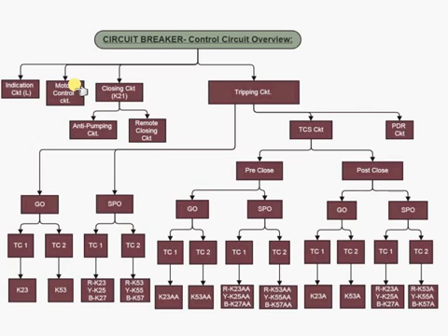Now this motor starts automatically when the spring is discharged, because the spring charge limit switch contact is placed in the motor circuit, so that when the spring is discharged, supply is extended to the motor, and when the spring is charged, the supply to the motor is cut off.